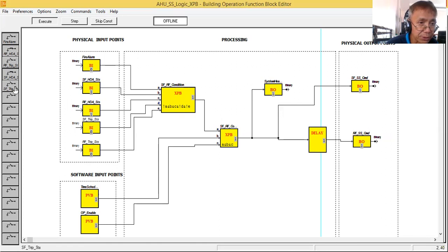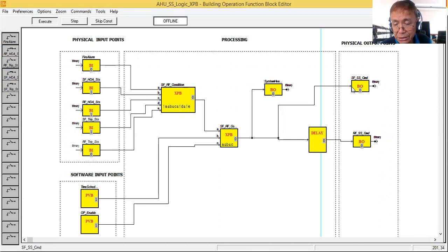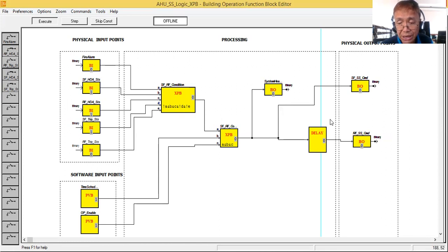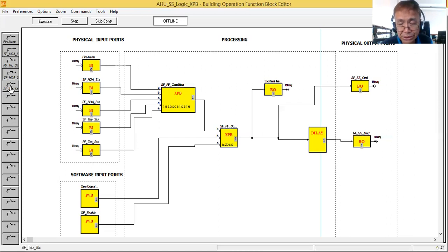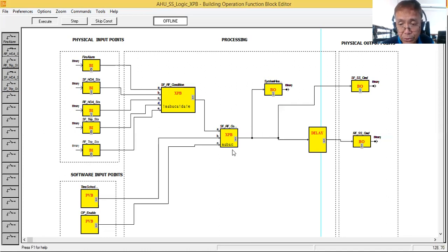Now let's simulate a trip on one of the fans — I'll simulate a trip on the supply fan. As you can see, our program shuts down the air handling unit. Now let me remove the supply fan trip, and as you can see, our control logic restarts the air handling unit.